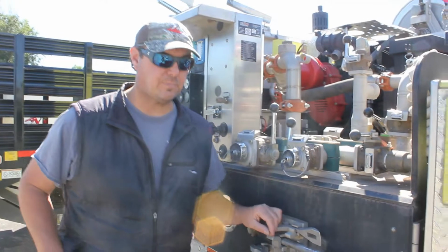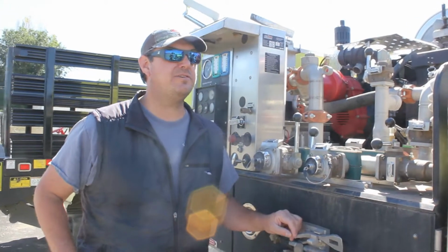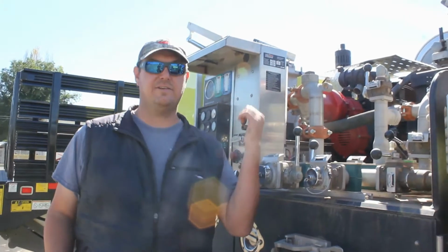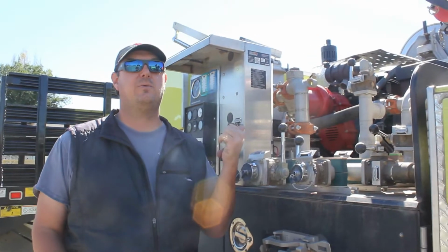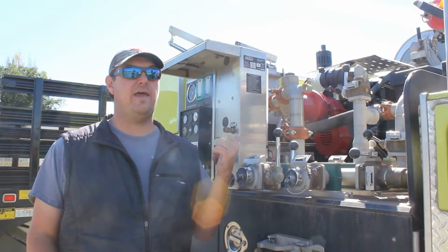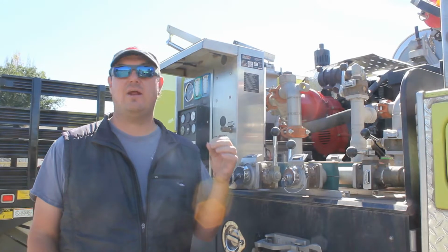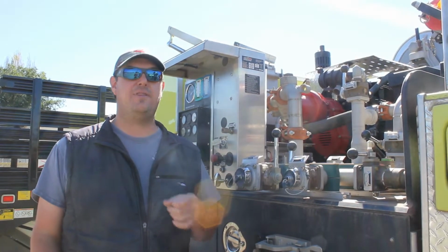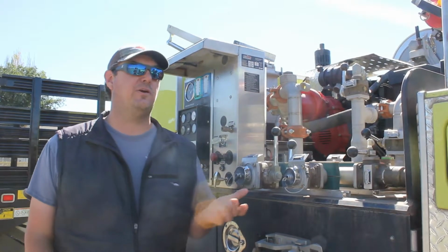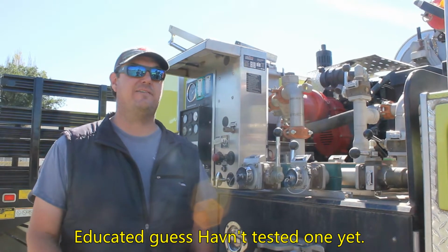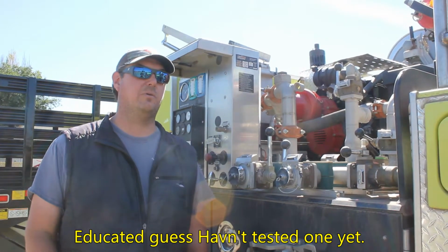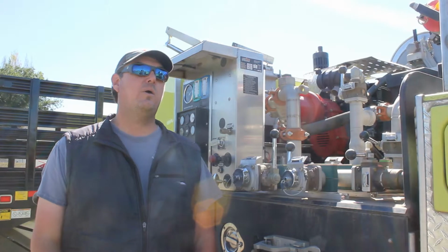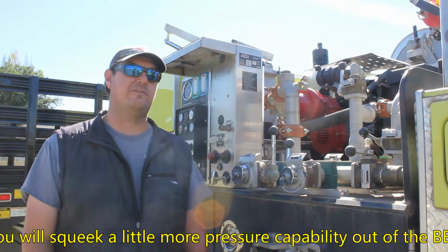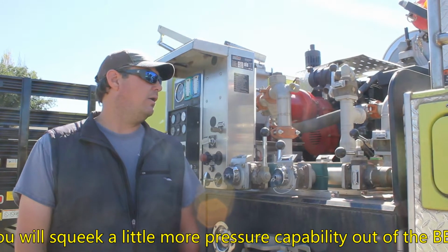The performance-wise, they're pretty close. These guys are going to give you a little bit more pressure, which is what we usually want. And when you get more pressure, you're going to end up a little less volume. But you can get up in that almost 400 PSI range and still be moving 3 to 5 gallons a minute. So you're still running one nozzle way the hell up on top of that hill. Whereas the Darleys probably aren't going to do that for you, at least not as well.